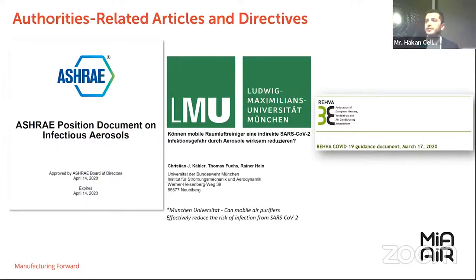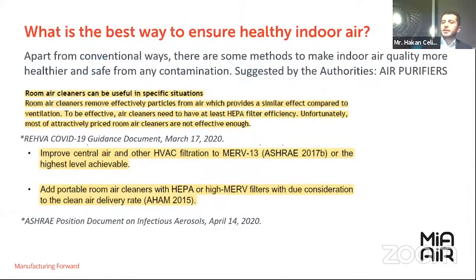Also, the Munich University has published an article, and they are saying that the air exchange rate of the air purifier has to be between 4 to 8 times. So if you are using an air purifier, it has to circulate the air in 1 hour around 4 to 8 times. That's clearly mentioned by REHVA. Each and every air purifier is not effective against virus contamination.